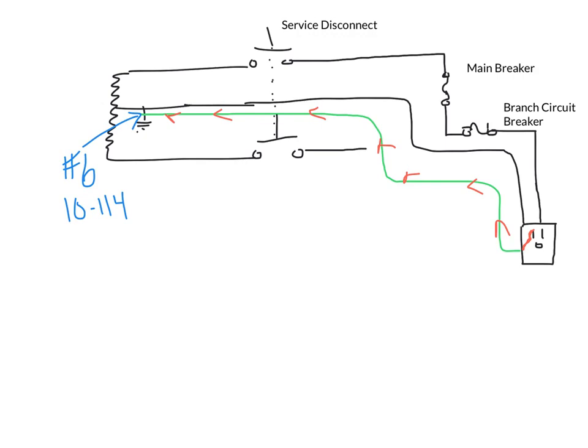But it doesn't. Why would fault current want to go to ground through a small conductor to essentially a big resistor, which is the earth? The earth is roughly 5,000 ohms per cubic meter of resistance with no path for current to flow. It doesn't make sense. Ohm's law tells us current takes the path of least resistance, and that's what bonding allows us to do. Bonding goes back through our system bonding jumper, which is the connection between XO and case in either your panel board or your transformer.